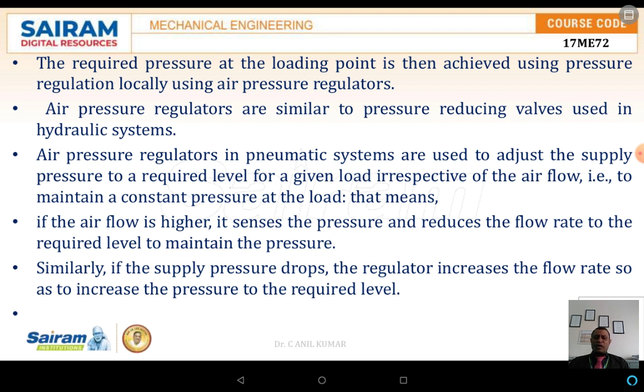The air pressure regulators are similar to pressure reducing valves used in hydraulic systems. The pressure regulator in a pneumatic system is used to adjust the supply pressure to a required level for a given load, irrespective of the air flow, to maintain a constant pressure at the load end or application end. If the air flow is higher, it senses the pressure and reduces the flow to the required level to maintain the pressure. Similarly, if the supply pressure drops, the regulator increases the flow rate so that the pressure is maintained at the required level. For that reason, the air regulator is another basic essential component in the line.